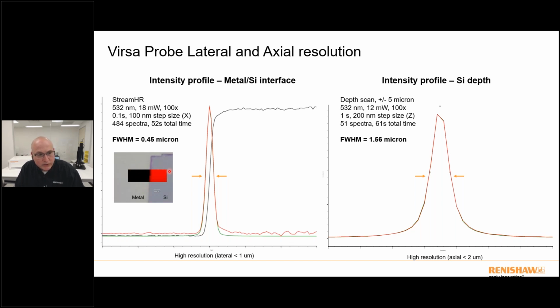Going from a metal surface to a silicon surface, and then simply plotting along the length of a horizontal profile of the intensity of the silicon band. So this black part of the spectrum is the intensity of silicon as we transition from metal to silicon. If you do a first derivative on that and you measure that full width half max, you're getting about 0.5 micron. So that's what your lateral resolution test would be.